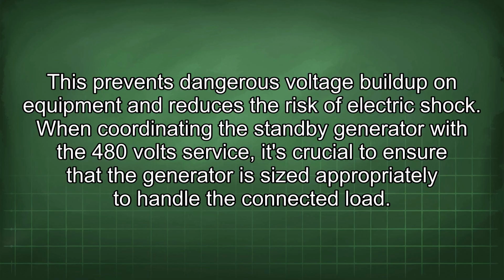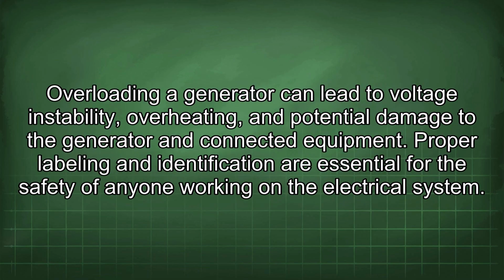When coordinating the standby generator with the 480-volt service, it's crucial to ensure that the generator is sized appropriately to handle the connected load. Overloading a generator can lead to voltage instability, overheating, and potential damage to the generator and connected equipment.